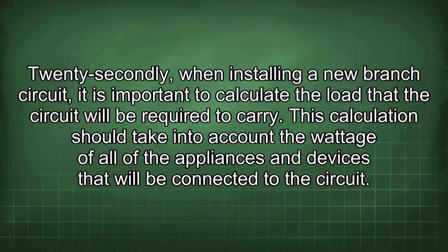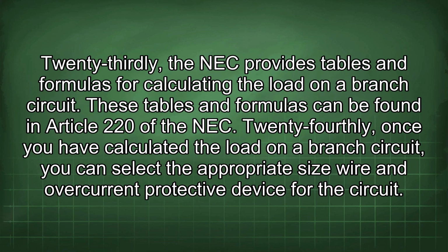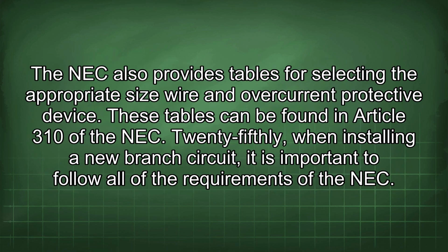connected to the circuit. Third, the NEC provides tables and formulas for calculating the load on a branch circuit. These tables and formulas can be found in Article 220 of the NEC. Fourth, once you have calculated the load on a branch circuit, you can select the appropriate size wire and overcurrent protective device for the circuit. The NEC also provides tables for selecting the appropriate size wire and overcurrent protective device. These tables can be found in Article 310 of the NEC.